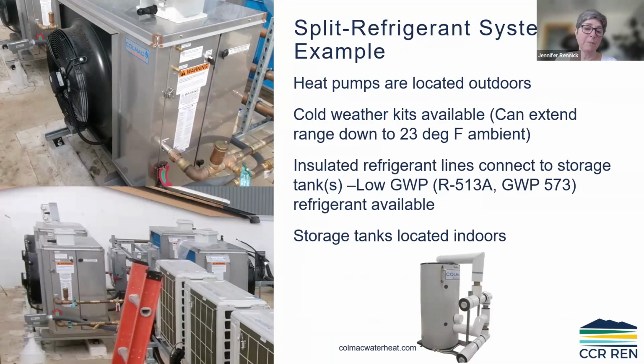But the heat pumps are located outdoors, in this case up on a roof, and then the tanks were located indoors. The refrigerant line that connects these outdoor condenser compressor units is going to be heavily insulated, and there are storage tanks located inside, a little bit insulated like that picture shown down at the bottom. And you can get low global warming refrigerants for it now. And then there are special kits you can order so it gets down to like 23 degrees Fahrenheit.